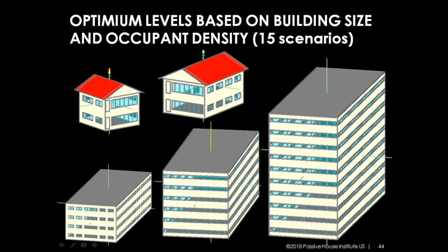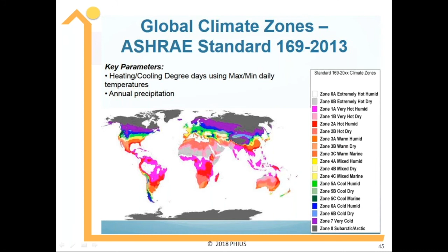The new standard for now has been calculated for the 17 global climate zones under ASHRAE. That works because it tracks with the heating degree days and cooling degree days. We still have to do more work to dial in the specific peaks - the design temperatures can vary dramatically within these ASHRAE climate zones, so they're not as homogeneous. But for the time being, we're sticking with these 17 climate zones, with more work to come to dial in the peak loads.